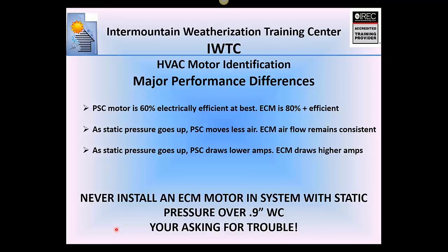Never install an ECM motor in a system with static pressure over 0.9 inches of water column. Wade's personal threshold is 0.8 inches. Mobile homes are often poor candidates for ECM retrofit because their duct systems typically have high static pressure that's difficult to correct. If static pressure is over 0.9 inches, an ECM is a horrible choice — it will not fix the system and will cause callbacks and problems.